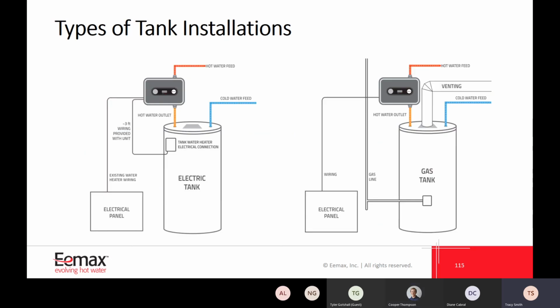Typical installations: the hot water tank, electric tank on the left, uses the existing hot water heater wiring to power the auto booster. This means it's a one-trade install—no need to call in an electrician to install auto booster on an existing electric tank.